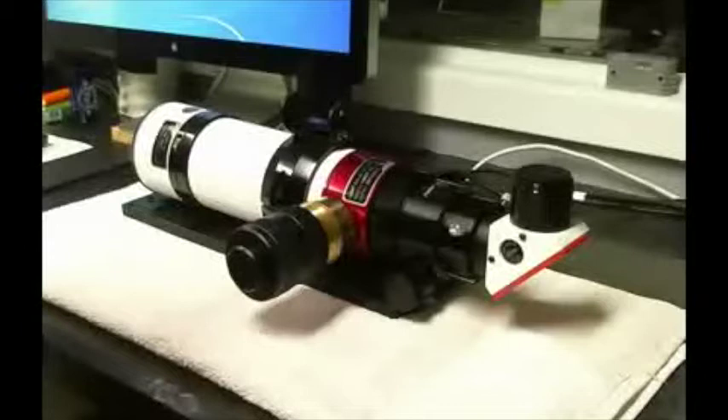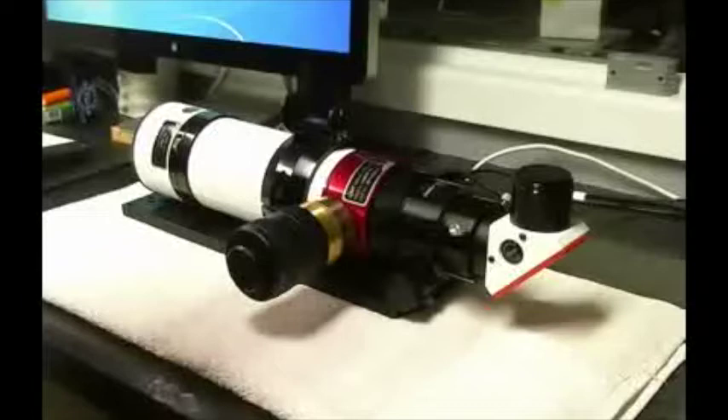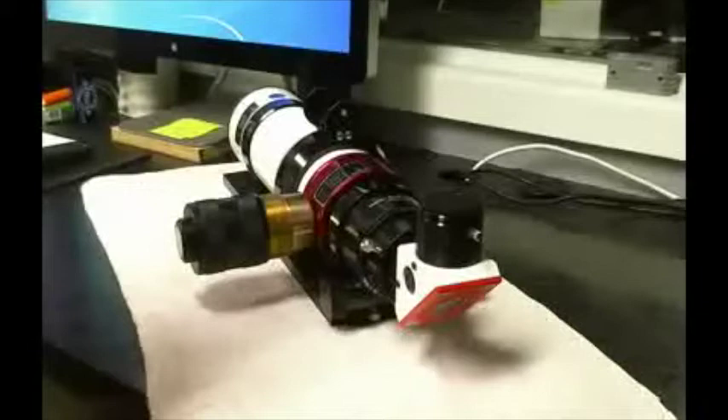Hello Mr. Craig, how are you? I wanted to chronicle what we're checking out here today on this Lunt Solar Scope. I got your email and your recommendation as far as checking out what seems to be the problem. I'll explain to whoever might be watching: I can make the adjustment on the double stack unit and it seems to lose pressure after 10 or 15 minutes. I can initially get a very nice surface detail, but after 10 or 15 minutes it ends up having 30 or 40 percent of what it should. I believe we've got a leak in a seal or something similar, so I'm taking this apart for the first time.